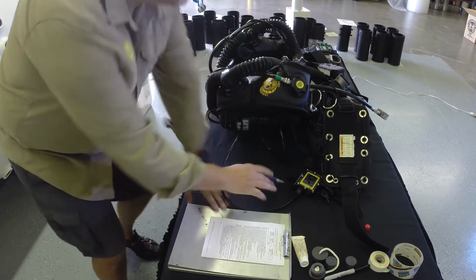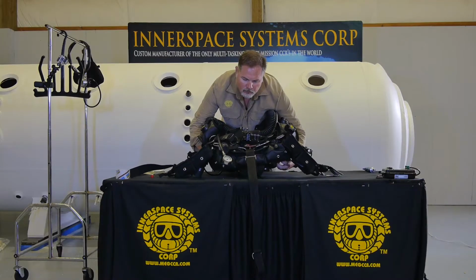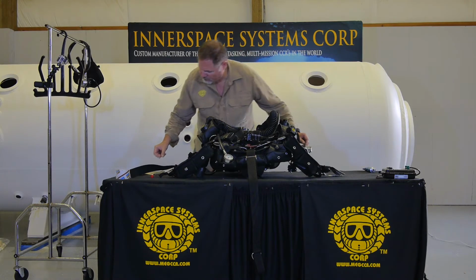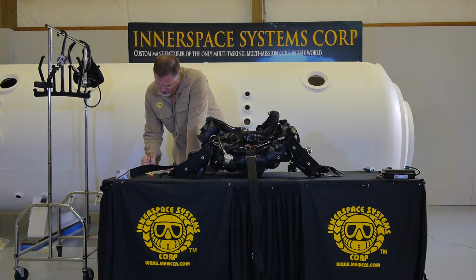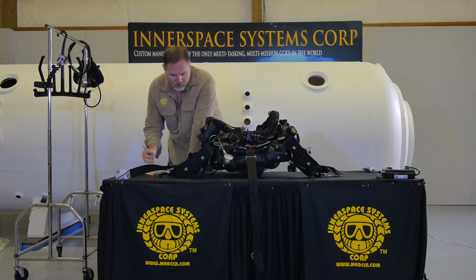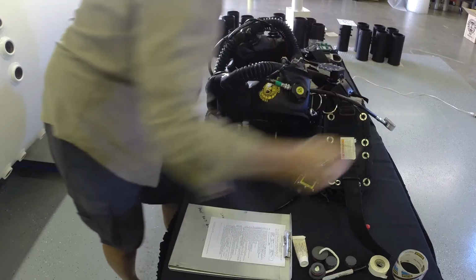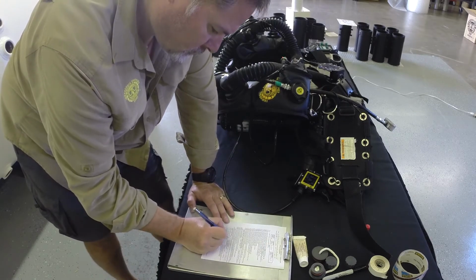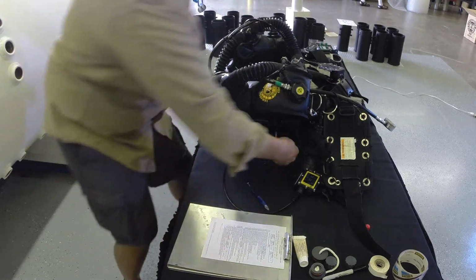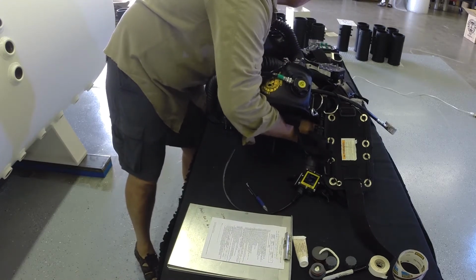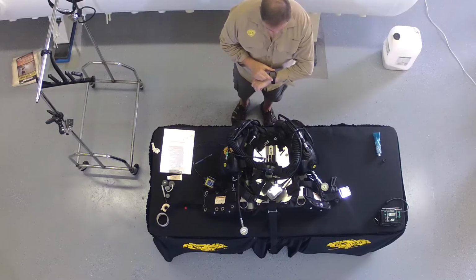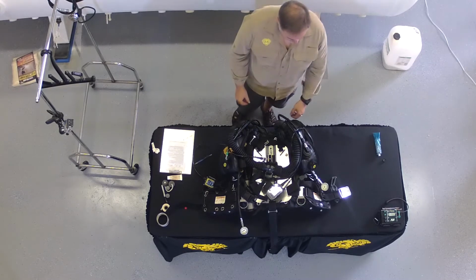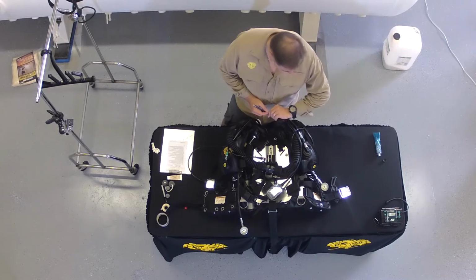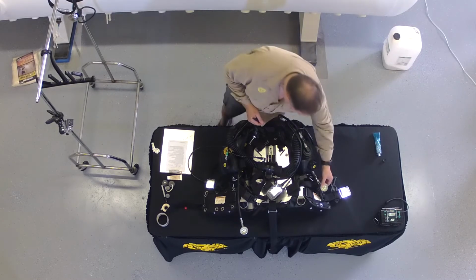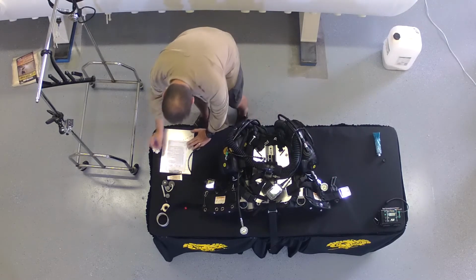After it's turned itself off, it's at 0.7, 0.75. I've done that a few times. I'm happy with it. Sign off on number 29. Number 30 is optional. Conduct a linearity check at a max O2 in cylinders. And basically that's doing a reverse O2 flush, running oxygen backwards through the loop. And what I should see on the display should match what I have in the oxygen cylinder. I didn't do that because I already calibrated.